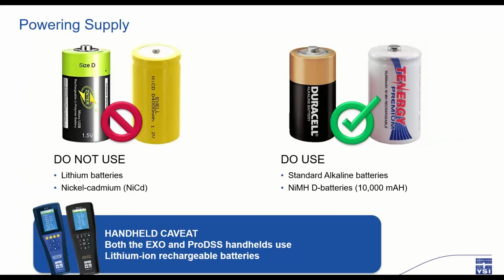Another battery-related issue that comes up often is the use of lithium or nickel-cadmium batteries in a sonde. In concept, it sounds great. What could be bad about longer-lasting batteries? But it turns out that the voltage of these batteries is actually much higher than the traditional alkalines and can actually fry some of the electronic components inside the sonde.